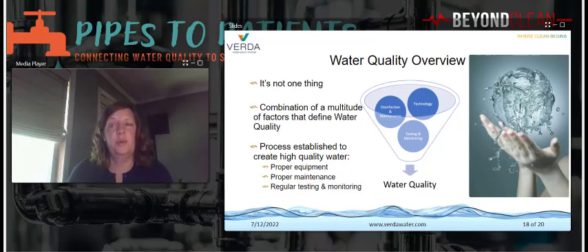Spreading the accountability and responsibility of SPD water quality across multiple organizations can be a recipe for failure. SPD is responsible for testing the water at point of use, but not necessarily for fixing any issues. Water Maintenance Department manages the water feeding the SPD, and they're likely not educated fully on the requirements of TIR 34, the ranges of acceptability in the water quality parameters, how to address or fix problems when you're out of range. So how do you keep it all together?